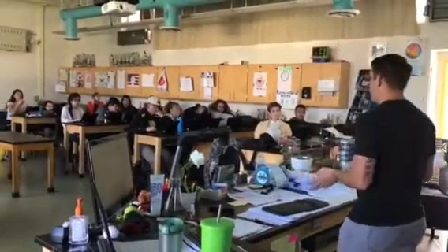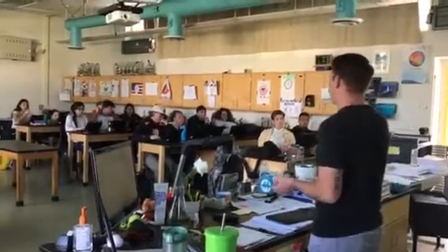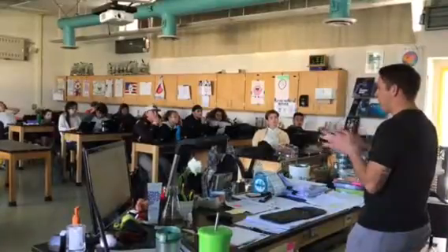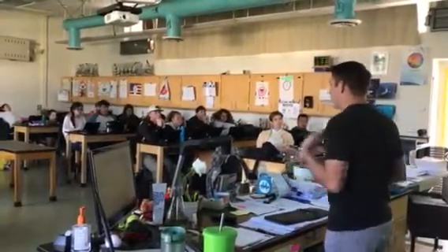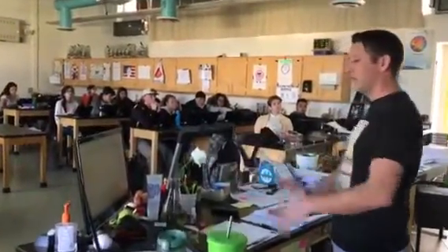Like for example, when you start the instrument, it takes a while for the fan to spin up and actually pull the correct volume through the instrument to make it accurate. So those typical first couple minutes of data, we usually just shear off. We can also do this thing called outlier tests, and I can teach all this stuff in the future, but right now we'll just focus on the Excel stuff.